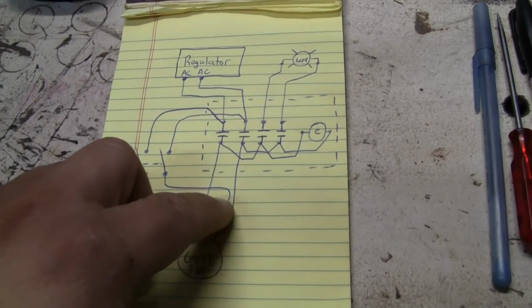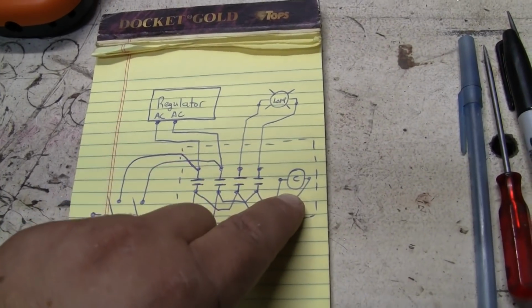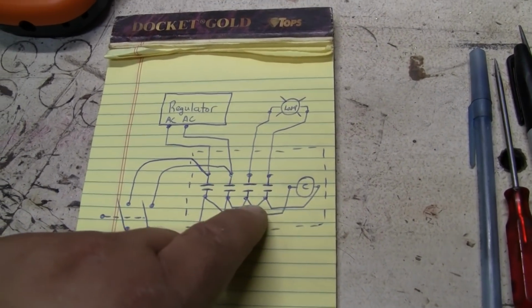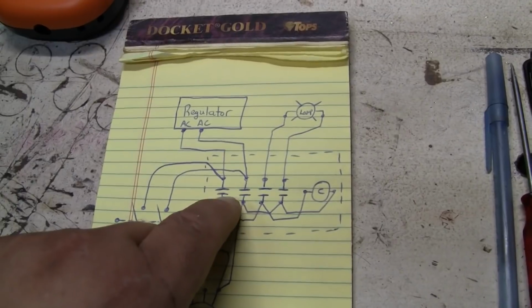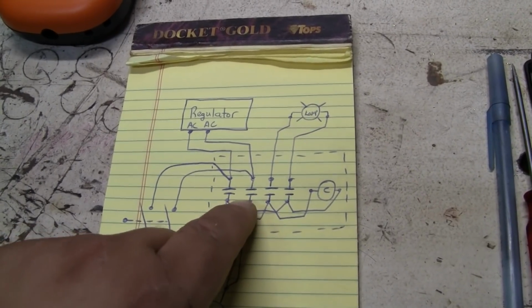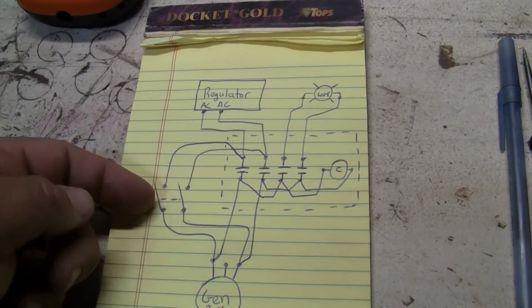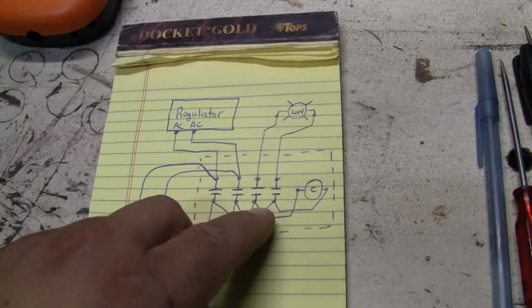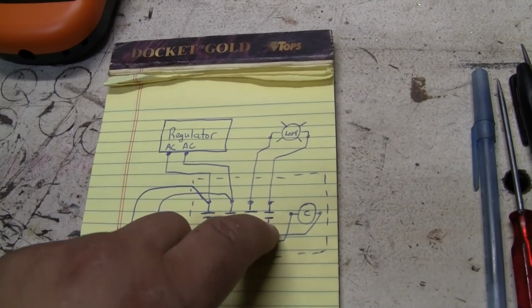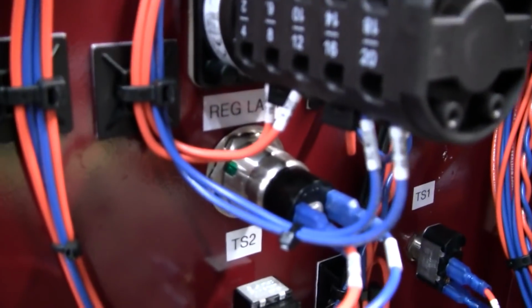Once the gen's output reaches the pickup point of the relay's coil, the relay contacts close. This pair here closes, which shunts out the toggle switch, so you can then release the toggle. These other 2 contacts close, which lights up this indicator light right here. See that? I have it labeled regulator lamp.